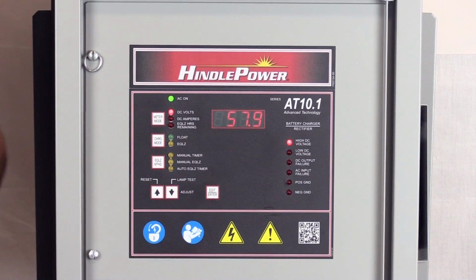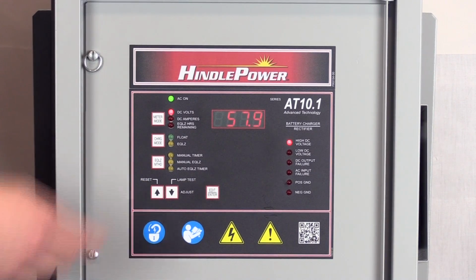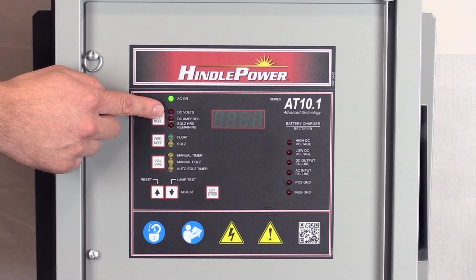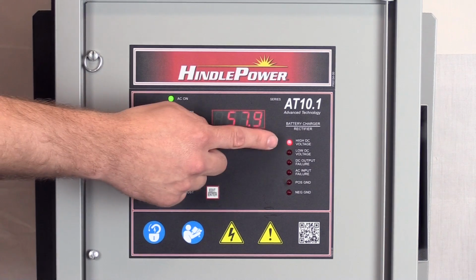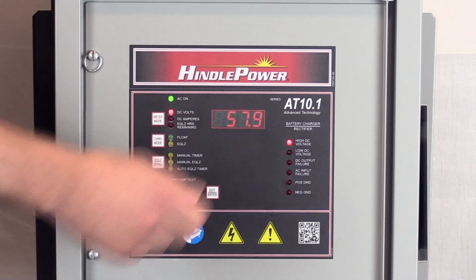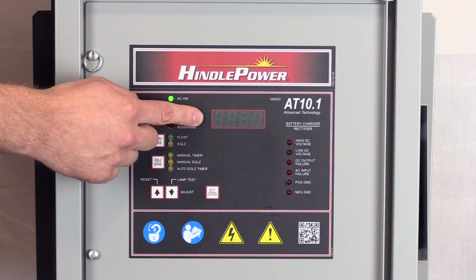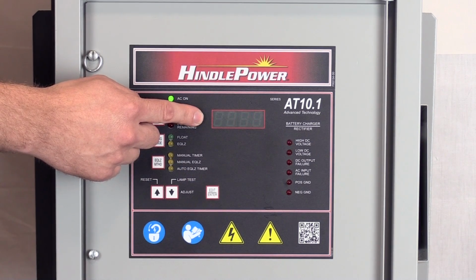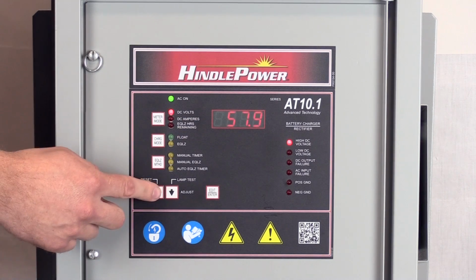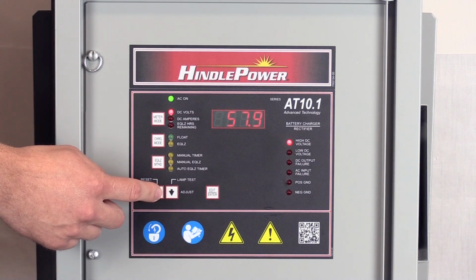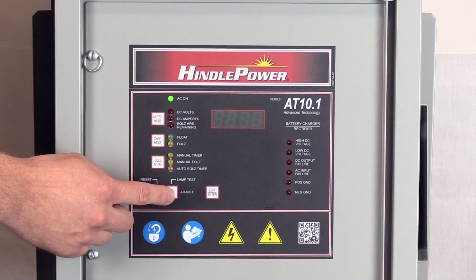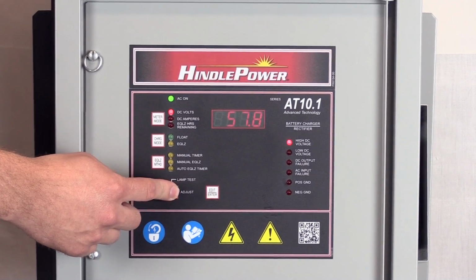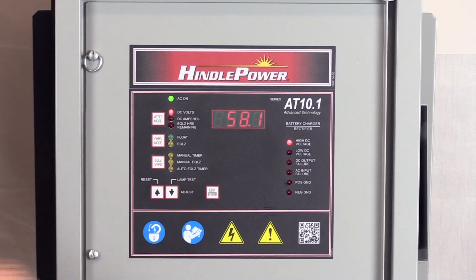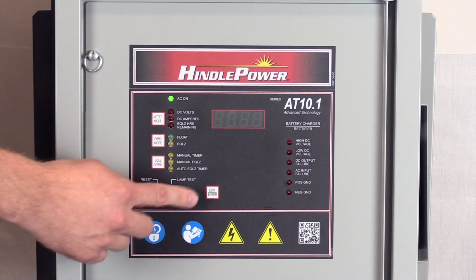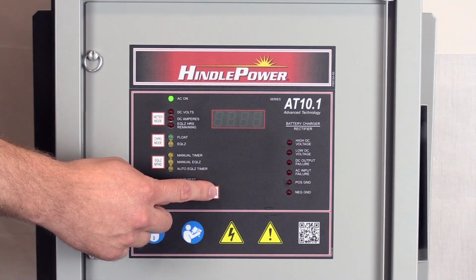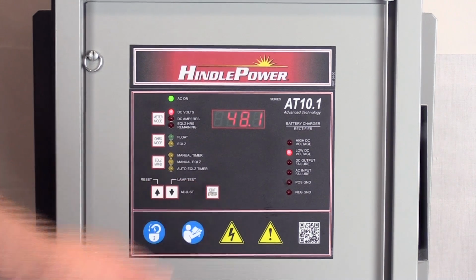The next parameter is the high DC voltage alarm. The red DC volts LED will flash. The red high DC voltage LED will flash. And the LED display will flash the high DC voltage alarm. Use the arrow keys to adjust the set point. Press the Edit Enter key, and this will save your changes and go on to the next parameter.